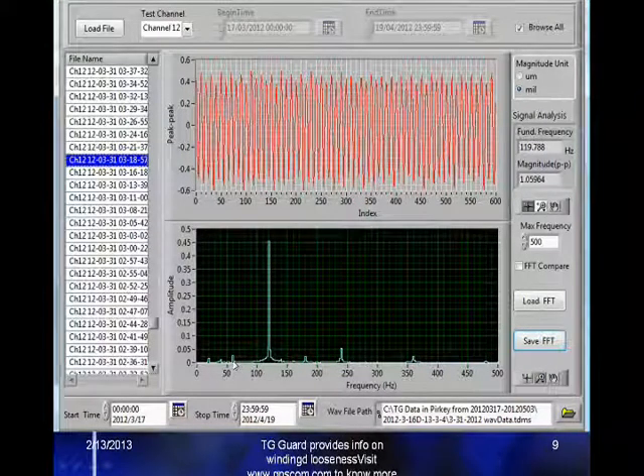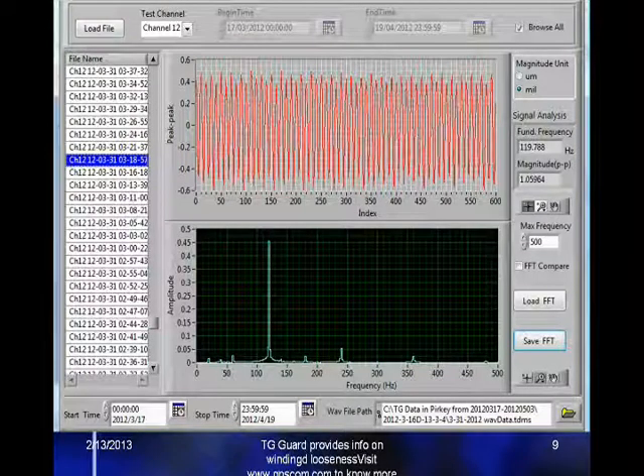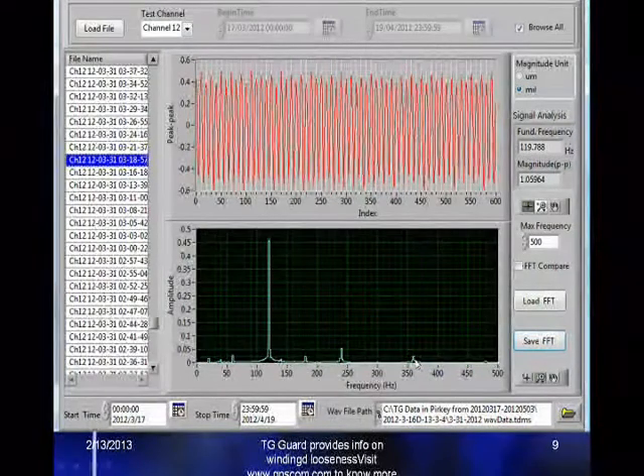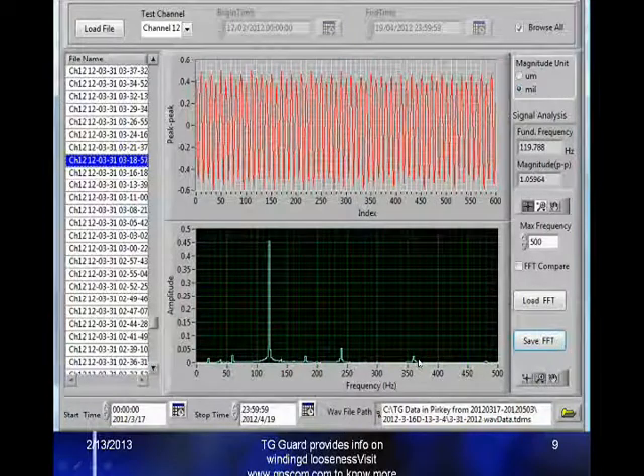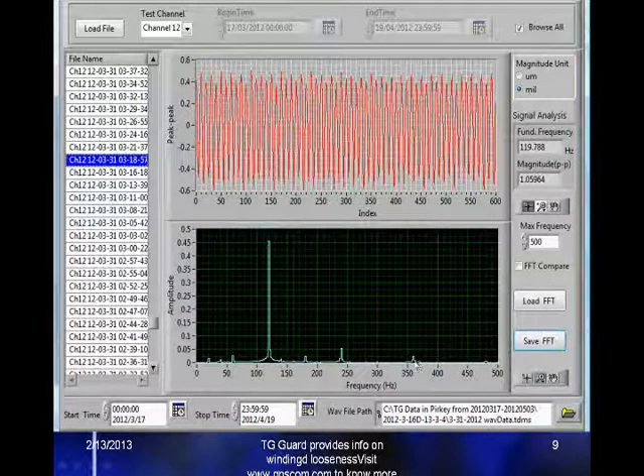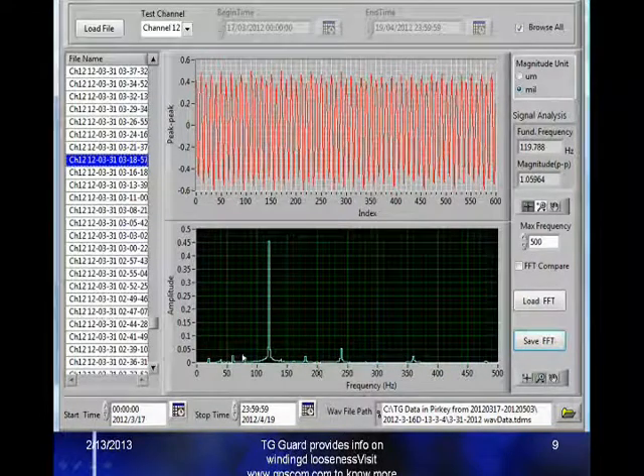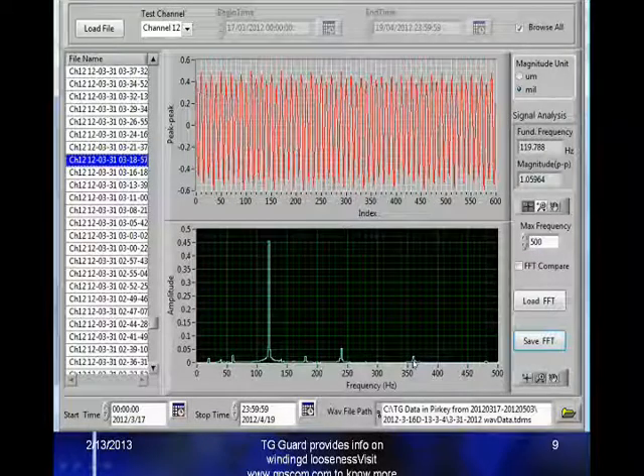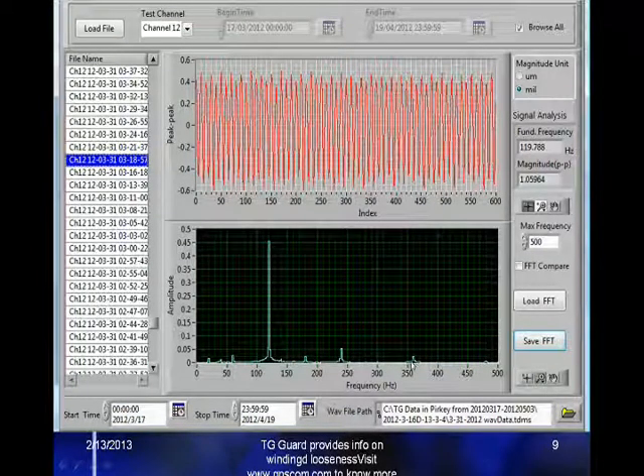We suspect that there is small vibration transmitted from the rotor, but we will be discussing that more with the power plant. And of course, 120, 240, 360, there is a little bit of harmonics. Since we already calibrated the sensor before we installed it, these reflect real differences, because when we did the calibration with a programmable shaker, we didn't see the harmonics. So these harmonics are generated from the actual vibration of the machine.